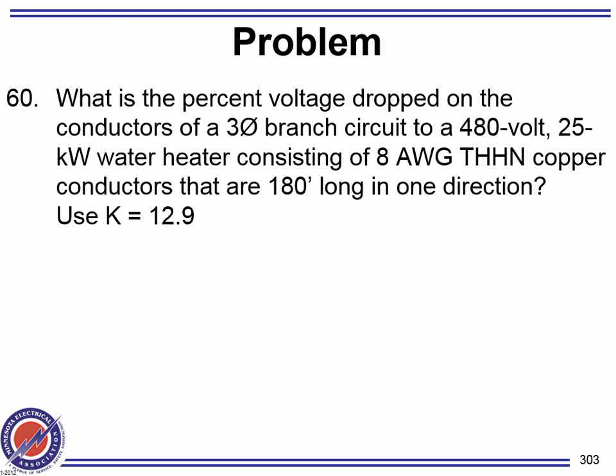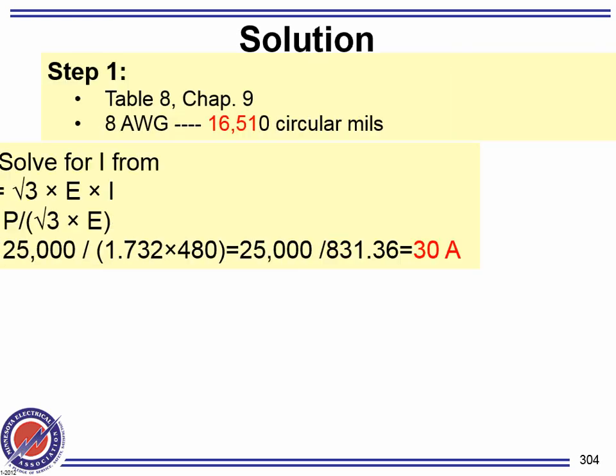All right. The only difference in this example, guys, we need to find the voltage drop. It's a 480 3-phase. Here's a conductor given. It's a K. The distance is given. The only thing that's not given, or given in a different format, is the load. The load is given in kW. So what would you do? Piece of cake, find the load in amps. You can't put the 25 in the formula. You need amps. So first find the load in amps.